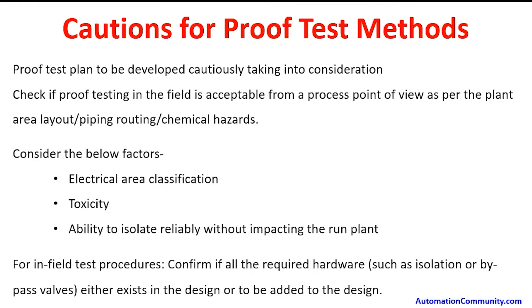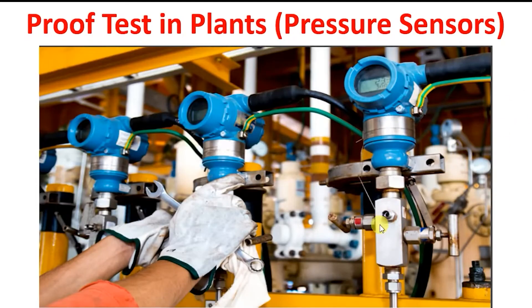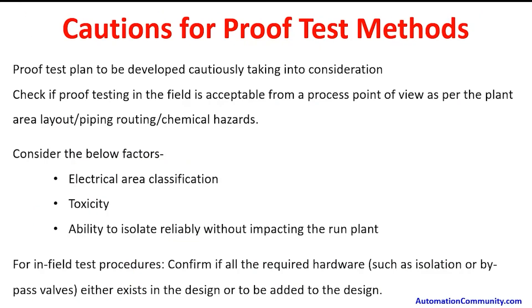Caution for proof test methods: proof test plans are to be developed cautiously, taking into consideration whether proof testing in the field is acceptable from a process point of view — as per the plant area layout, piping routing, chemical hazards, etc. Before taking a proof test, it must be ensured that flushing of the instrument line is safe, as the line may need to be drained, which could cause a small pressure change. This should not impact the running process.